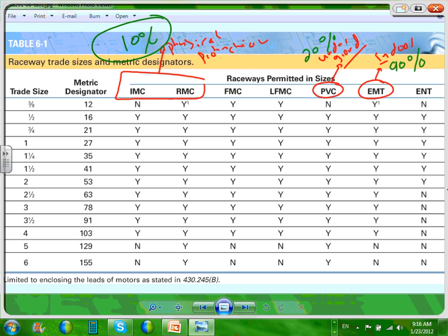So, logically, where the heck would I use flexible metallic conduit? Everybody knows what a flexible metallic conduit is. Do I have one here? Flexible metallic conduit is a conduit that's flexible, and it's metallic. What do you do with this? Would you wire a building like Dunwoody with flexible metallic conduit? Yes. Would I call you below average if you do that? Yes. Is it the best wiring method to wire everything, all branch circuits and feeders, with flexible metallic conduit? No. The major use for flexible metallic conduit, guys, is tied to equipment. Connect to equipment.